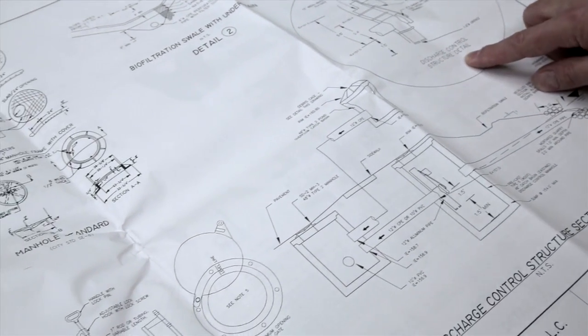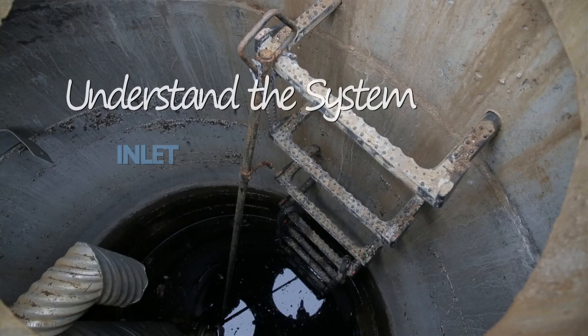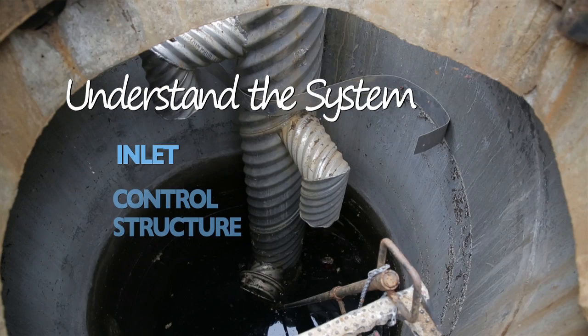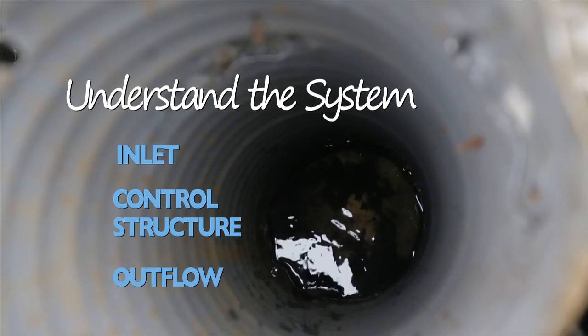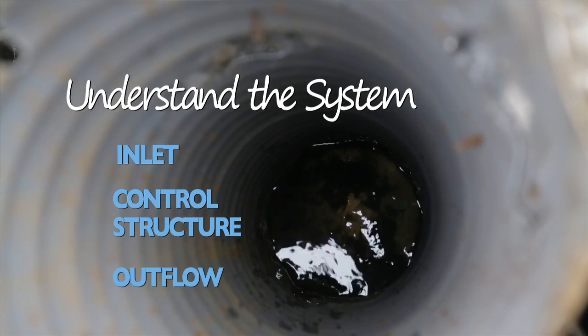So when you pop that lid, you'll be able to see the inlet where the water comes in. You'll be able to identify the control structure itself, if it's a vertical pipe or if it's a weir, and you'll be able to see and identify where the water exits the structure. So by reviewing the plans in the office, it's going to give you the basic understanding of the system. And by understanding the system, you'll be able to identify potential problems and save time and money in the long run.